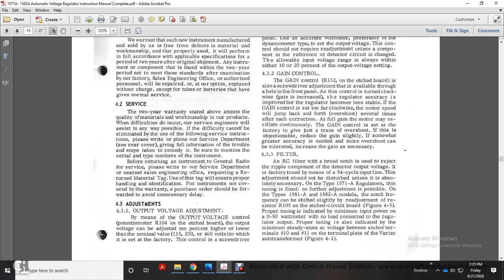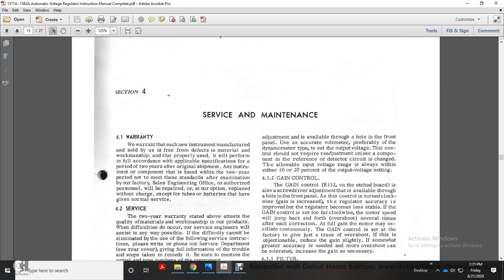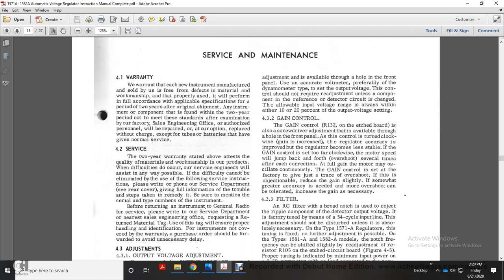4.3 Adjustments. Output voltage adjustment: the output voltage control is the potentiometer R104 on the etched board. The output voltage can be adjusted ten percent higher than the design normal 115, 230, or 460 volts, which is reset at the factory. The control is a screwdriver adjustment available through the hole in the front of the panel. An accurate voltmeter, preferably of the dynamometer type, is used to set the output voltage of the control, but readjustment should not be required unless the components of the reference for the detector circuit are changed. Allowable input voltage range is always within 10 to 20% of the output voltage setting.